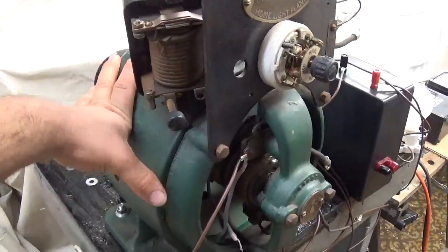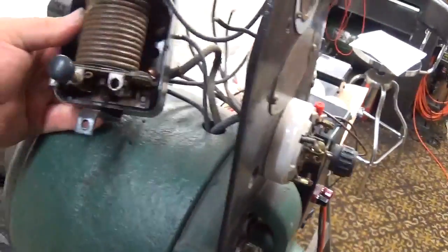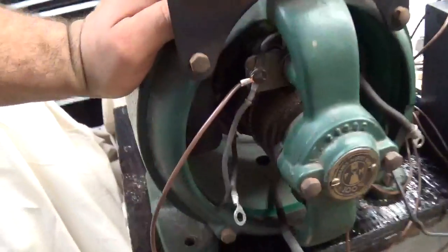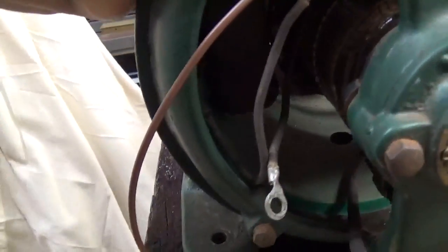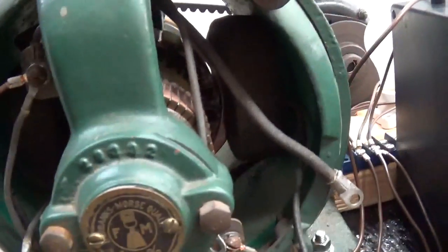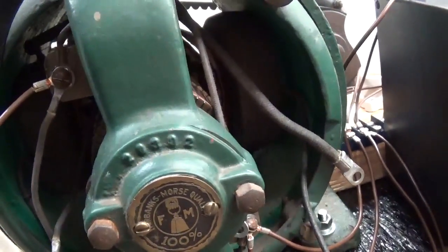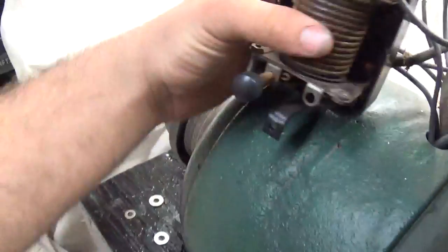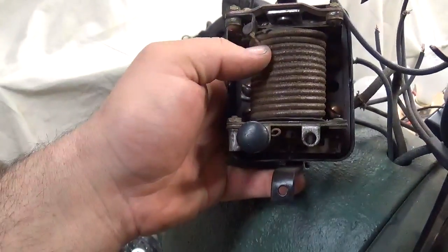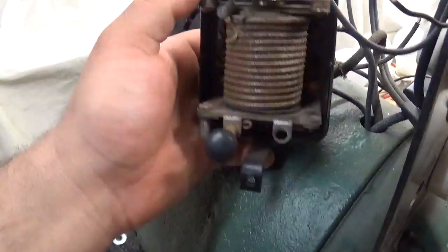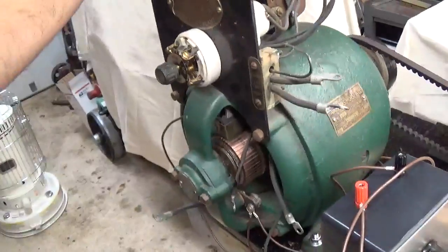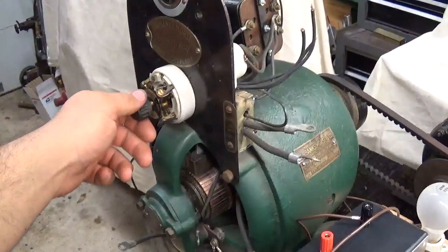So what he did was he took the generator head to a fella to have it rewound. And when I say that, they wound new field coils. It's a two pole generator, it's a really simple generator. They rewound the armature. I don't think they touched the voltage cutout. They just cleaned it up. And they rewound the field resistor.